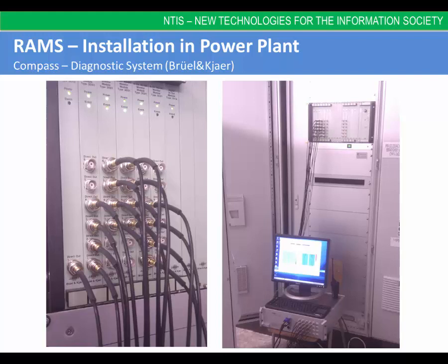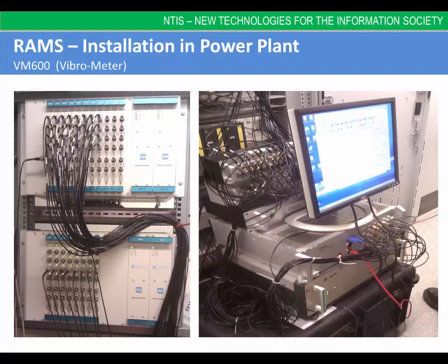As you can see in the picture, it was a mobile installation and the problem to solve was the rubbing occurrence during cold starts of the steam turbine. The last example of installation shows another connection to the VM600 monitoring device from Vibrometer.